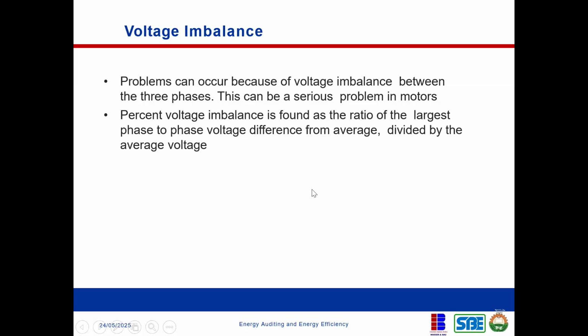Problems can occur because of voltage imbalance. When we talk about voltage imbalance, bear in mind that in a single phase system, voltage imbalance is not really a concern. We only talk about voltage imbalance in a three-phase system, and I'm saying this because most industrial equipment runs on three phase, especially industrial motors.